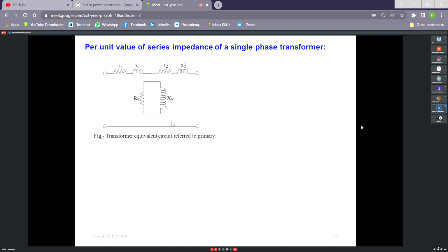So in distribution system, it may not be full load, maybe at half load, 1/4 load, but it is always at the loaded condition. It rarely happens that transformer is at no load. So for that reason, you know that when transformer is loaded, then no load current is negligible, 2 to 4% as compared to its rated current, or as compared to its full load current also it will be negligible.